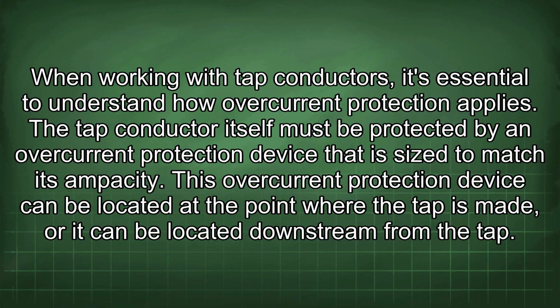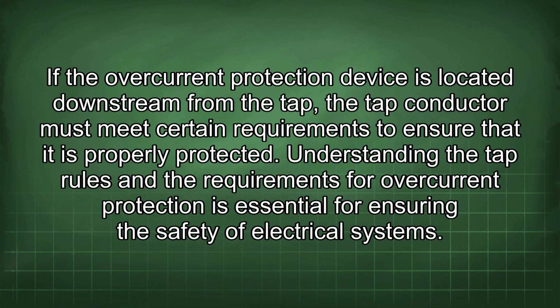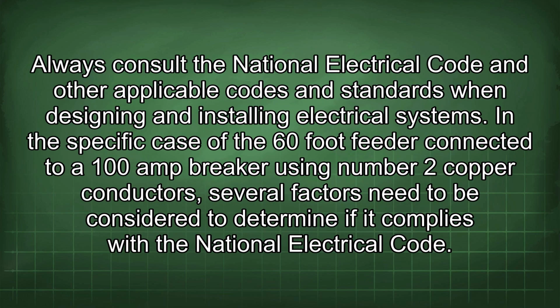This overcurrent protection device can be located at the point where the tap is made, or it can be located downstream from the tap. If the overcurrent protection device is located downstream from the tap, the conductor must meet certain requirements to ensure that it is properly protected. Understanding the tap rules and the requirements for overcurrent protection is essential for ensuring the safety of electrical systems. Always consult the National Electrical Code and other applicable codes and standards when designing and installing electrical systems.